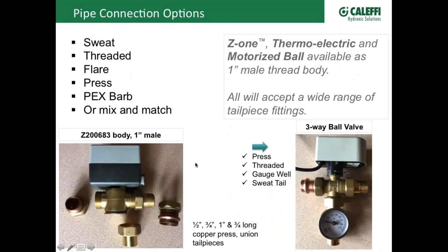All right, so here's a little bit about the pipe connections that I just mentioned. What we've been doing on our valves is putting this external thread, and that's called a G thread. I think it stands for gas thread. It's a common thread in Europe, but it's also common wherever you use a gasketed or a washer connection to the valve. So that's not a pipe thread, you can't just thread a coupling or a female adapter on there. You have to put a gasket or a fiber washer in between there.